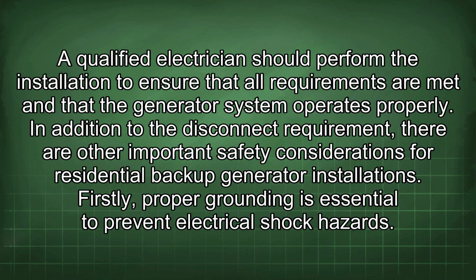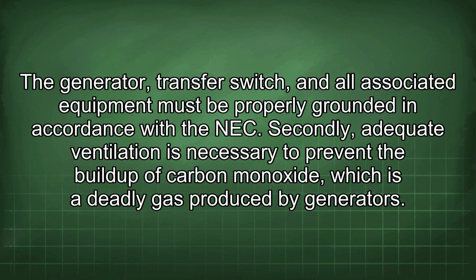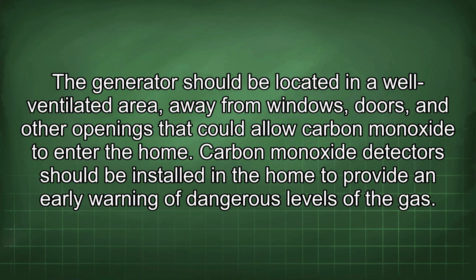Firstly, proper grounding is essential to prevent electrical shock hazards. The generator, transfer switch, and all associated equipment must be properly grounded in accordance with the NEC. Secondly, adequate ventilation is necessary to prevent the buildup of carbon monoxide, which is a deadly gas produced by generators. The generator should be located in a well-ventilated area, away from windows, doors, and other openings that could allow carbon monoxide to enter the home. Carbon monoxide detectors should be installed in the home to provide an early warning of dangerous levels of the gas.